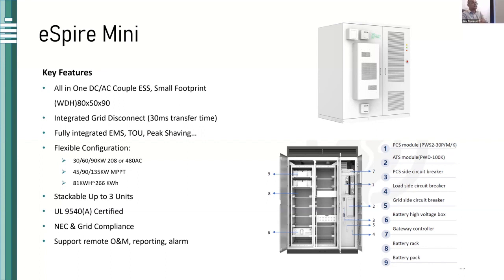But jumping into the specs on the eSpire, this ranges from 80 kilowatt hours up to 266 kilowatt hours on the battery side. And then on the inverter side, you have inverter choice of 30, 60, or 90 kilowatts. If you're going to be DC coupling the unit into the PV, the inverter that comes with the eSpire Mini can act as a PV inverter as well. That can intake PV anywhere from 45 kilowatts up to 135 kilowatts. The eSpire Mini is stackable up to 3 units. So if you do have a larger project than 266 kilowatt hours, certainly you could use the eSpire Mini for projects upwards of 700 kilowatt hours with the 3-unit stackability.